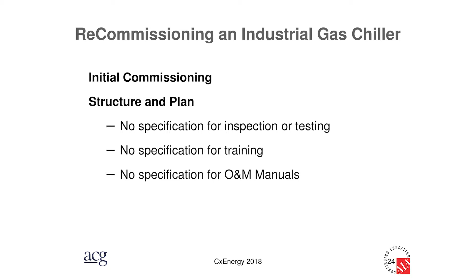So the initial commissioning structure and plan was really kind of scant. There weren't much in the way of specifications for the inspecting and the testing. There really wasn't any specification for training, although the manufacturer did give training to that first set of operators. Unfortunately, it got lost over the years. And there was no specification for good quality O&M manuals or system manuals. They did get a manual for the compressors themselves, but as far as the whole system, how it works, how it should be operated, none of that was available.